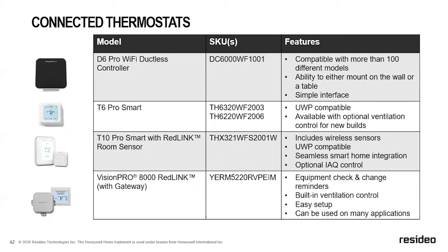So you could pull from it as need be, but if you put this on your truck, there's not one job you cannot do in a residential application or maybe even light commercial, as long as it's not a proprietary communicating system, that this can't get you out of a jam. So if I have a broken wire from my thermostat to my air handler, or maybe a broken wire from my air handler to my outdoor unit, we have modules for that. And if you look at how long it'll take you to pull new wire, or maybe it's not accessible, this kit will get you out of that jam.